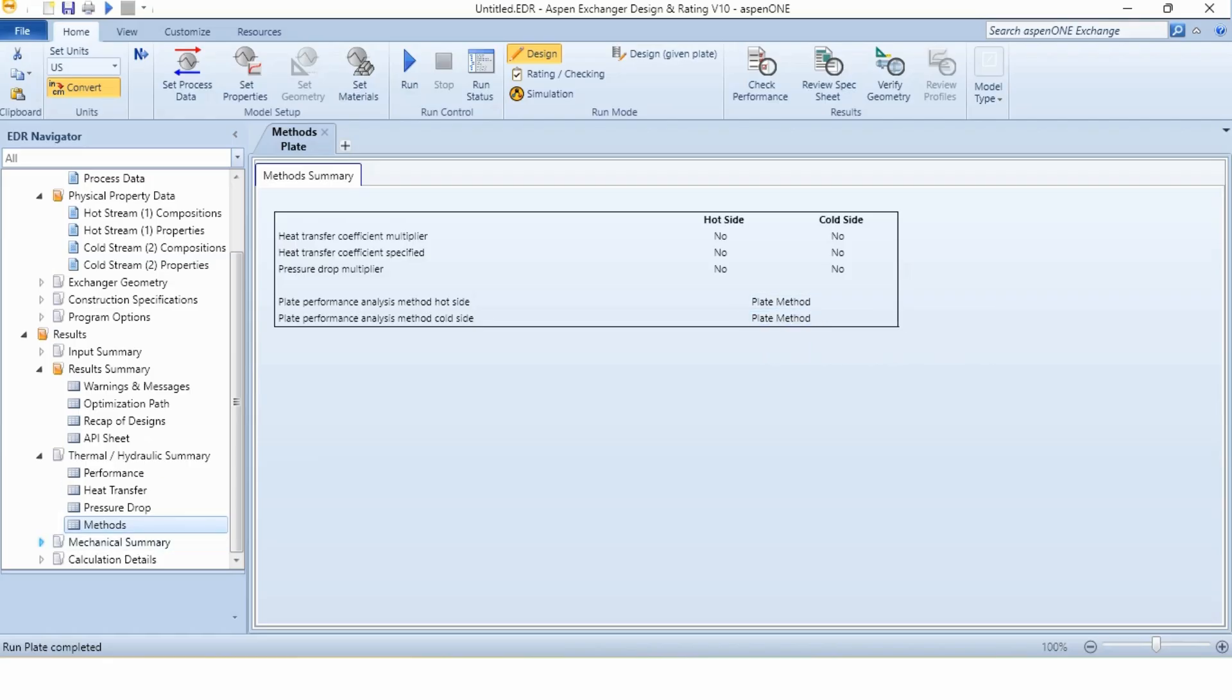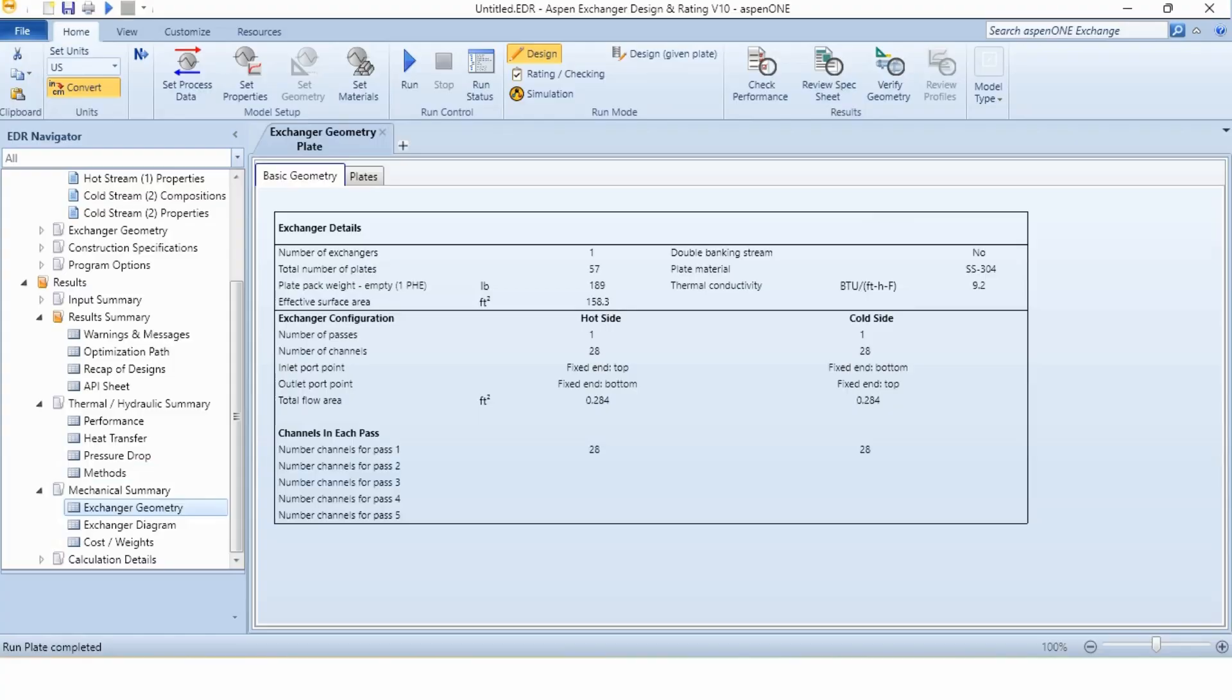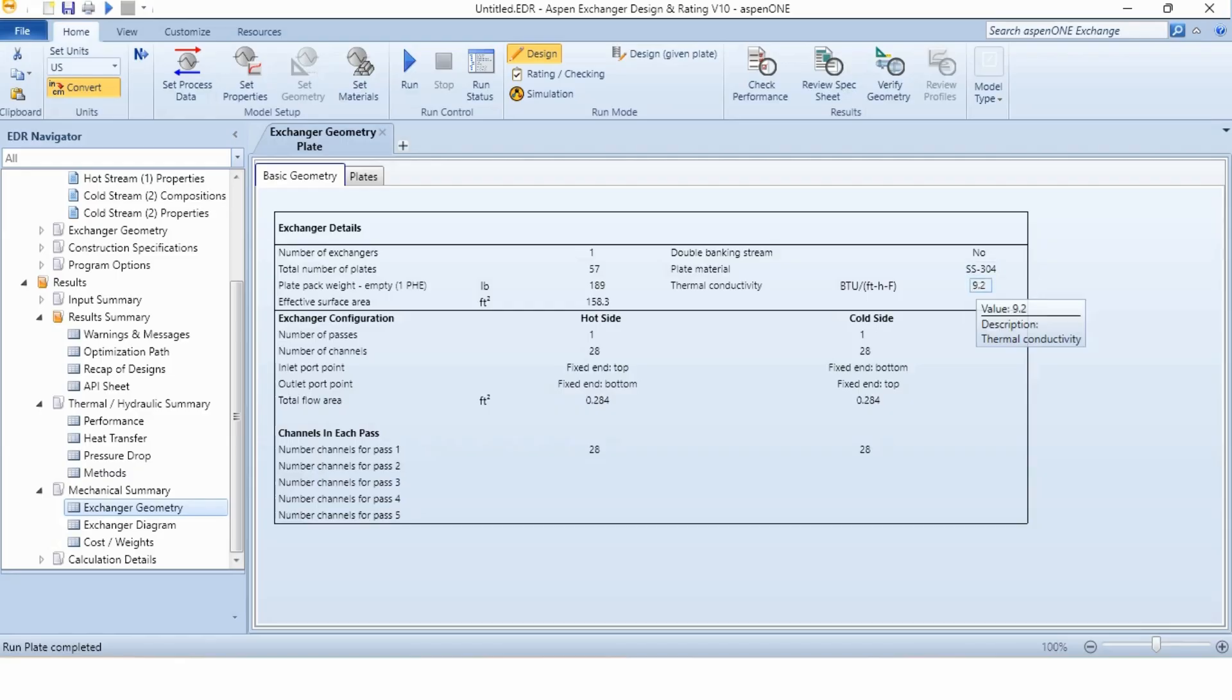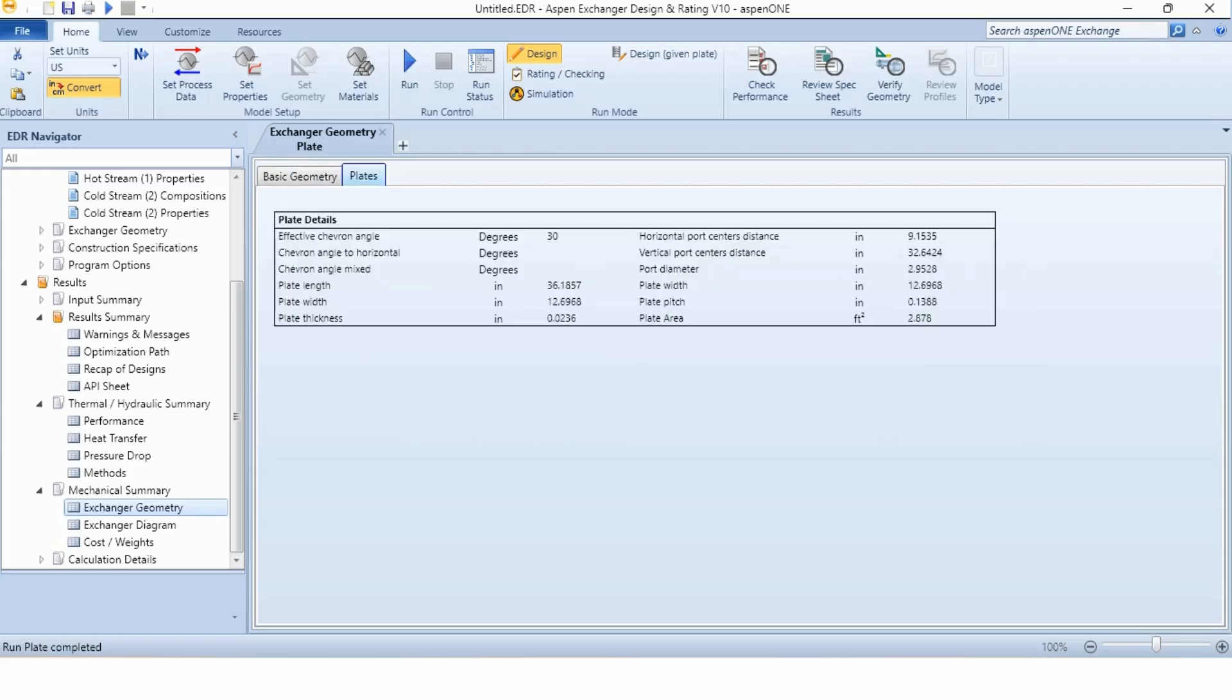If we go to the mechanical summary in exchanger geometry, this has been given to us. The number of exchangers are 1. The total number of plates is 57. The plate pack weight 189. The effective surface area 158.3. The plate material is stainless steel 304. The thermal conductivity is 9.2 BTU per foot per hour degree Fahrenheit. All the information about the basic geometry and then about the plates - length, the plate width, plate thickness, plate pitch, area width, everything is given. A detailed analysis is given over here.